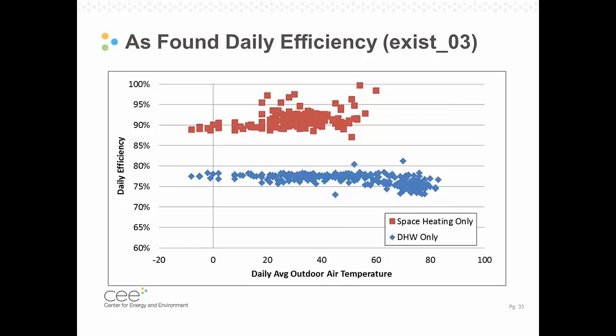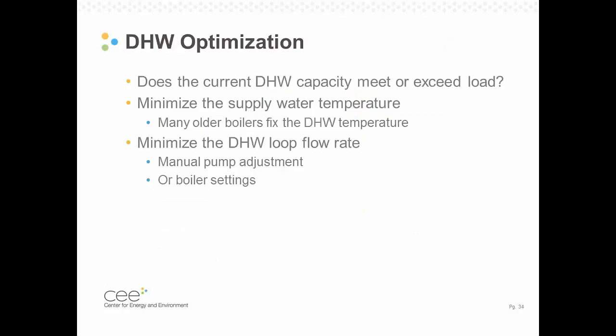And what you can see is that on the space heating side, we're getting those good return water temperatures like we mentioned in the last handful of slides, and we're seeing those 89 to 95% efficiencies on the space heating side. On the DHW side, we're seeing efficiencies in around the 77, 78% range. Much lower than on the space heating side, and that all has to do with that return water temperature and the system optimization. And so we're seeing those low DHW efficiencies.